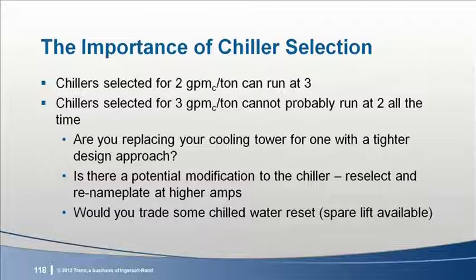Can you modify the chiller? There may be additional amps available on the motor that was selected for your chiller, but you have a nameplate today that corresponds to the original selection point, not the maximum operating point on the motor. Only the chiller manufacturer can help you find out if a reselection like this is possible without a physical modification to the chiller. At some conditions, you may be able to trade chilled water reset for additional lift capability when you absolutely must have it.